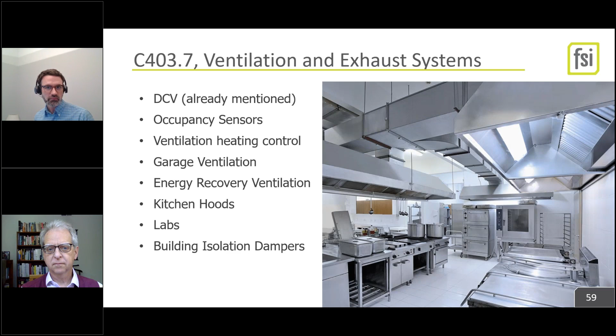So a lot of these are carryover from the previous code, but people are still catching on. In our code reviews, we see that. Basically, C403.7, you need to read it because it applies to a bunch of different building types. Like those building isolation dampers get missed all the time. At 25,000 CFM, you start isolating by branch of the building, so you can have that wing's open and that wing's closed, which is dead simple and just good money. It saves a bunch of energy, but gets missed all the time. Kitchen hoods now have their own rules about what airflow is allowable, sort of an efficiency for kitchen hoods. Most manufacturers will already beat it, but you've got to know. Go looking for the mechanical engineers in the room. If you haven't been super familiar, you should get familiar.